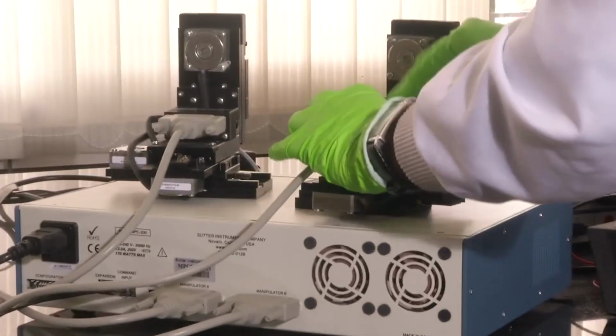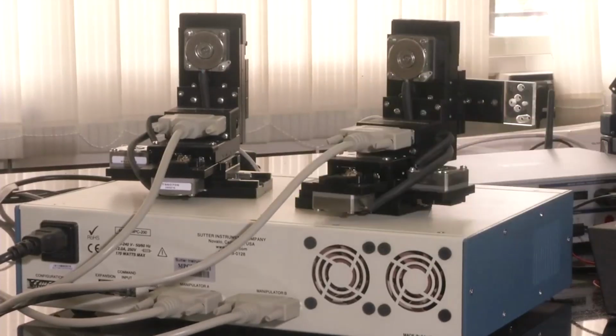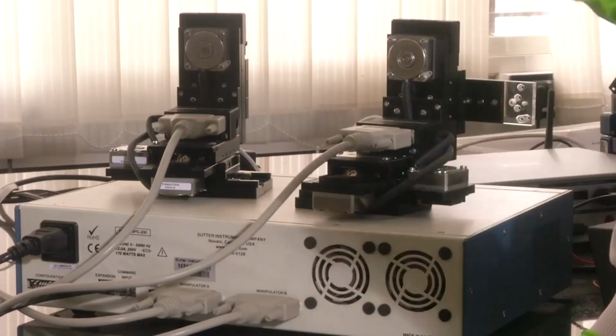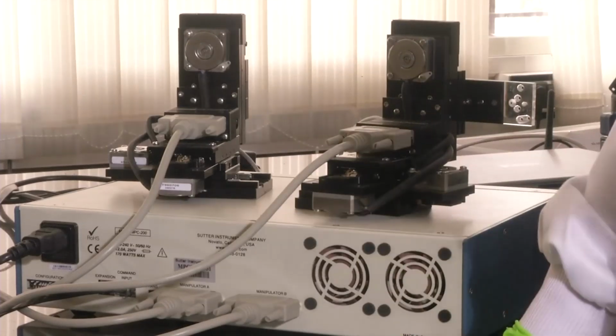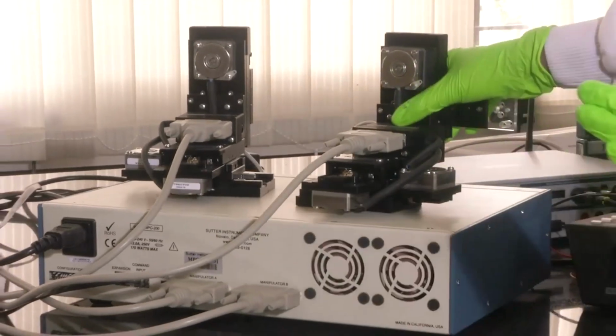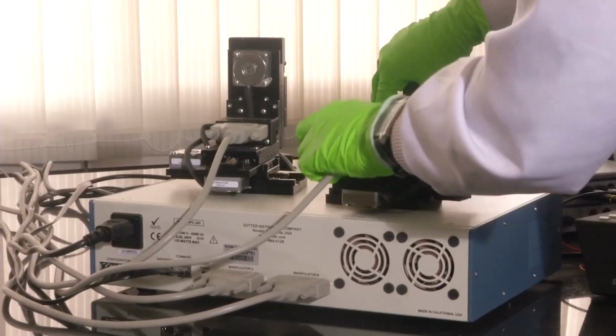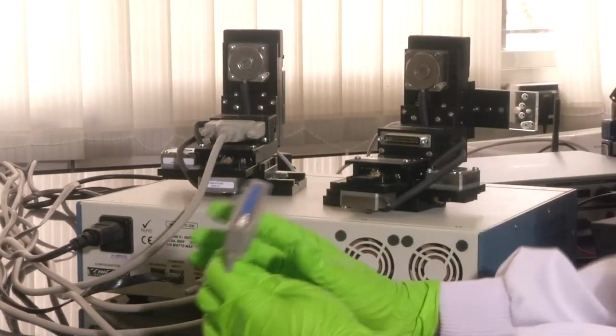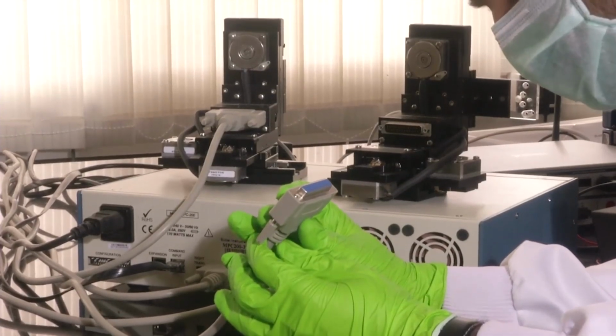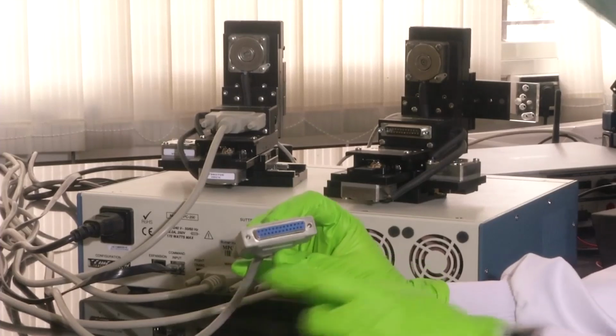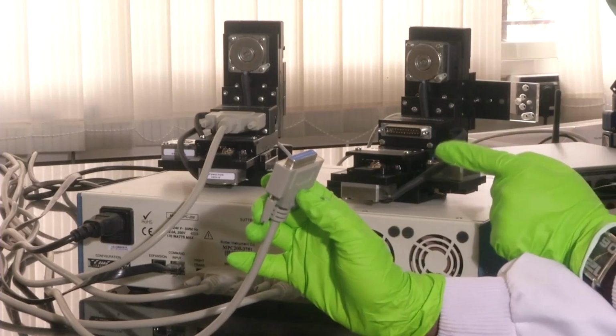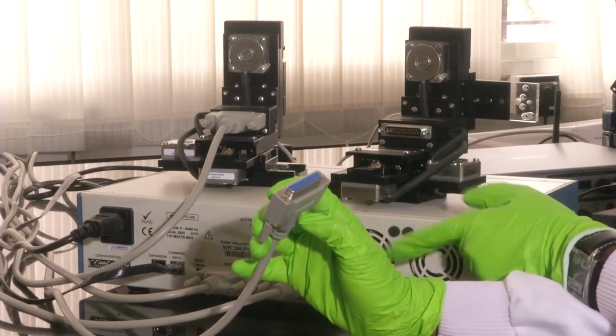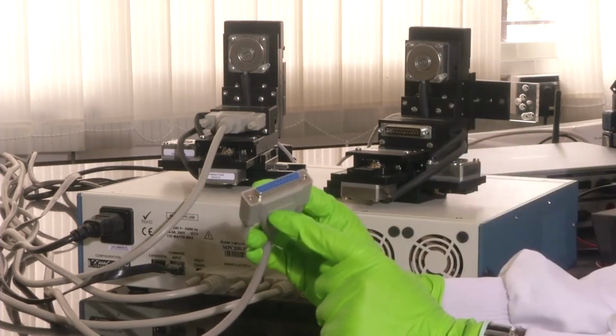So, this system is completely modular. By modularity, what we mean is that each important component of the system we should be able to remove and service, or look at as an individual whole. So, manipulator A and manipulator B come as separate entities which can be connected to the main unit through these connectors. I have taken out the connectors, if you see. So, this is a 25 pin connector, 24 pin connector. The entire communication, control data, measured data, all communications from the main unit through the control unit goes to the manipulator through this connector.